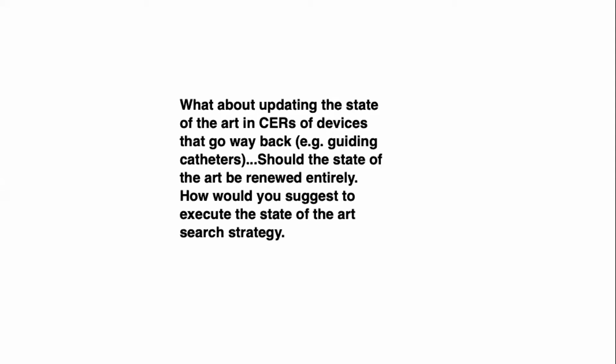Now, should the state of the art be renewed entirely? Well, that depends on if the prior state of the art is MedDev Rev 4 compliant and even MDR compliant. At Criterion Edge, we often update state-of-the-art sections from scratch, from previous CERs, because they're inadequate. They do not align with MDR compliance, and they certainly do not align with MedDev Rev 4. So be careful about just updating a state of the art. Look first to see if it meets the needs of the CER.